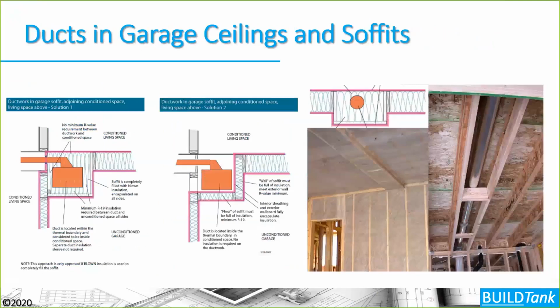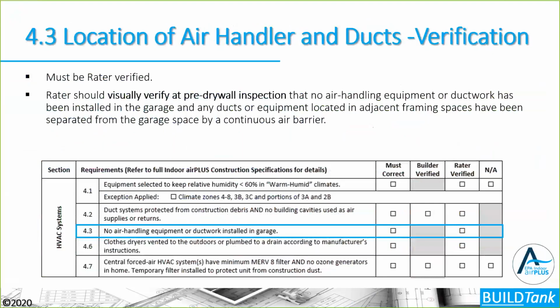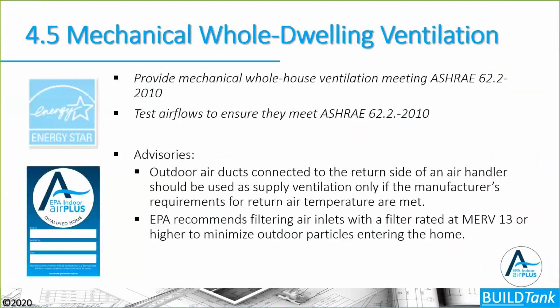So these are some examples of what the newer codes are allowing. If you're going to install the duct in the garage, you need some way of ensuring that the duct is inside the air barrier system of the house. No air handler equipment or ductwork installed in garage, so this is how that would be verified. Provide mechanical whole house ventilation systems and then test the airflow of those systems.